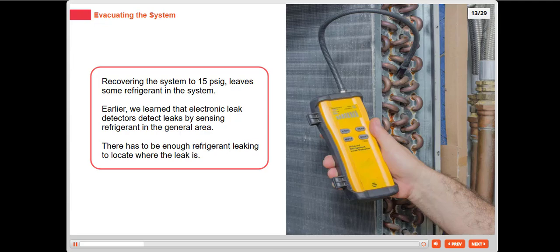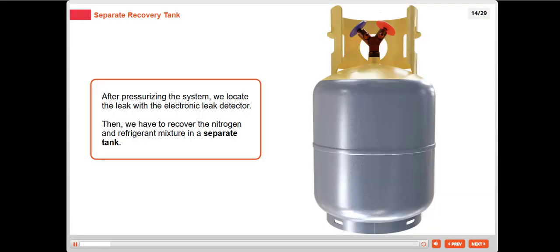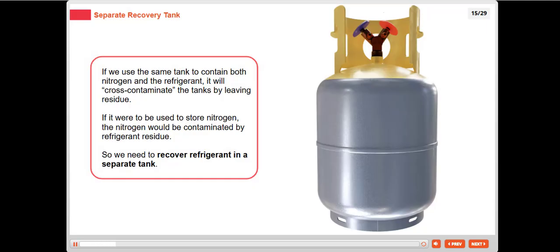Earlier, we learned that electronic leak detectors detect leaks by sensing refrigerant in the general area. There has to be enough refrigerant leaking to locate where the leak is. After pressurizing the system, we locate the leak with the electronic leak detector. Then, we have to recover the nitrogen and refrigerant mixture in a separate tank. If we use the same tank to contain both nitrogen and the refrigerant, it will cross-contaminate the tanks by leaving residue. If it were to be used to store nitrogen, the nitrogen would be contaminated by refrigerant residue. So we need to recover refrigerant in a separate tank.